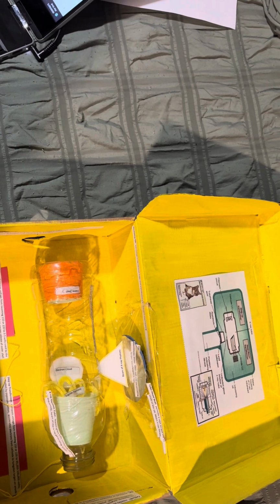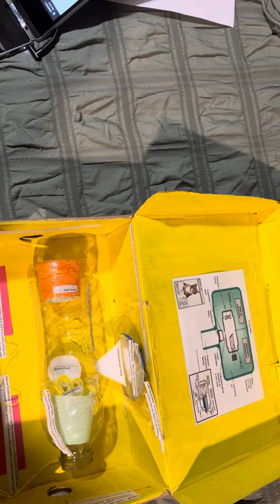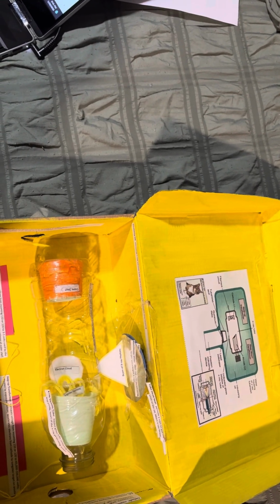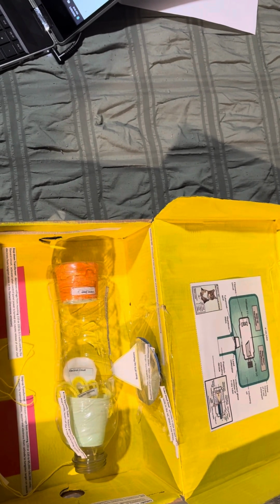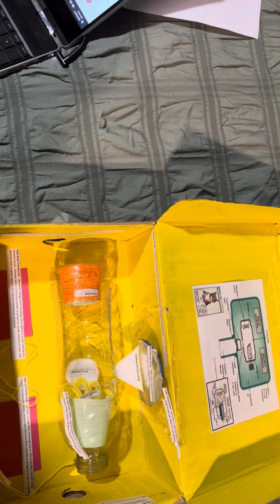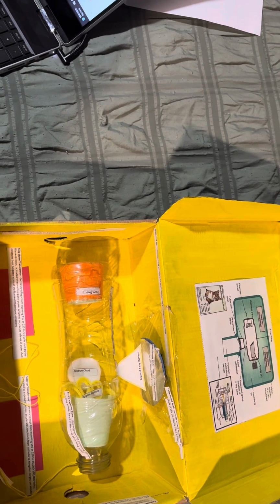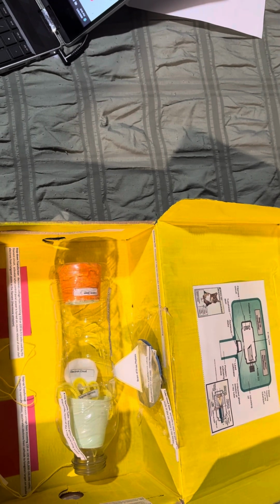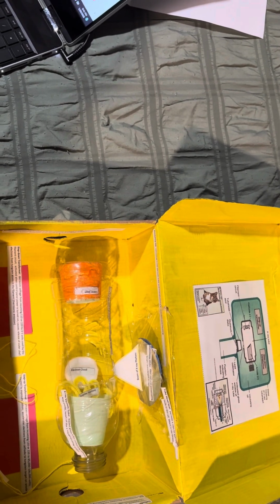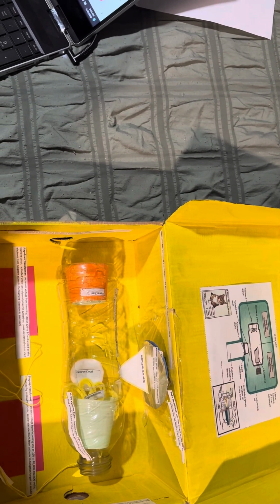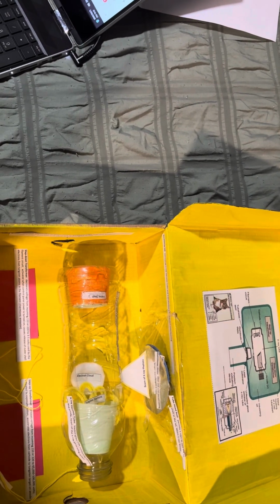the molybdenum cup, and the cathode directs the electrons to the tungsten target in the anode. The electrons travel from the cathode to the anode, and the heat that is produced is carried away by the copper stem and absorbed by the insulating oil. The x-ray travels through the unleaded glass window to the tube head and aluminum disc. Lastly, the x-ray beam is confined by the lead collimator and travels down to the PID opening.